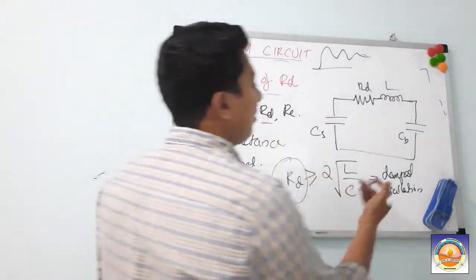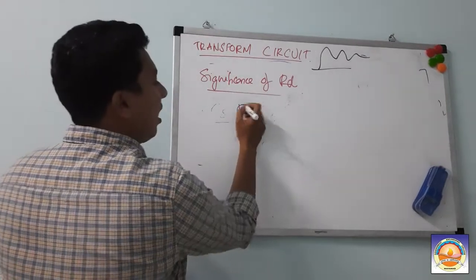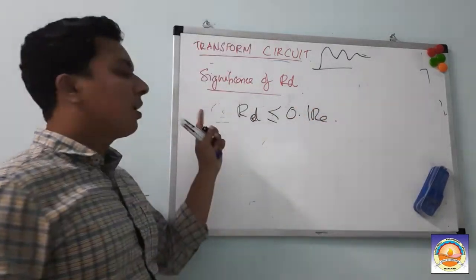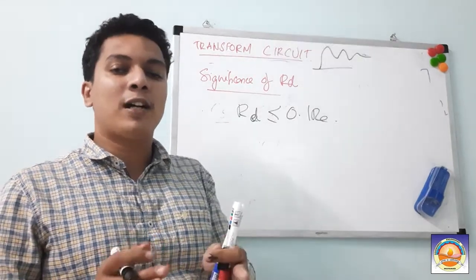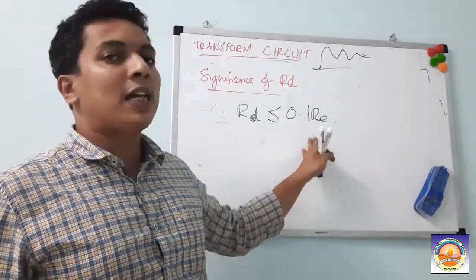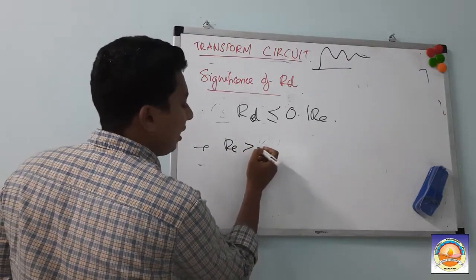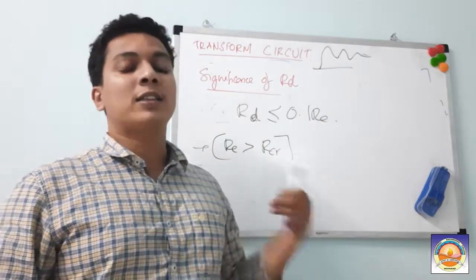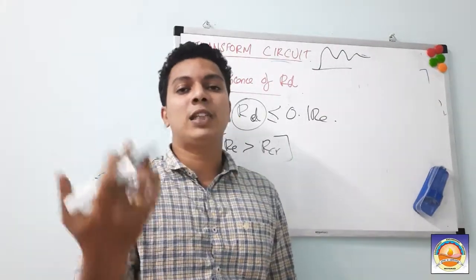For the discharge circuit, since Re is already 10 times greater than Rd, Re will always exceed the critical resistance — so no oscillation concern there. We only need to worry about the charging circuit. That is the significance of Rd as the damping resistor. In the next class, we will see multi-stage impulse generators in detail.